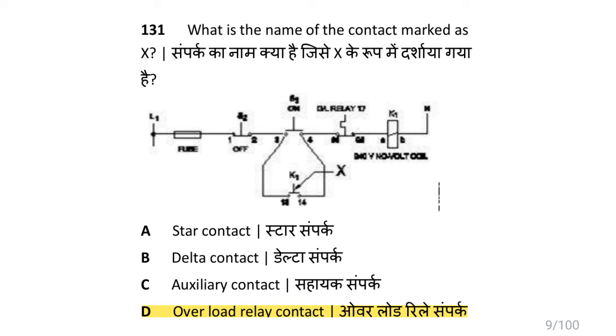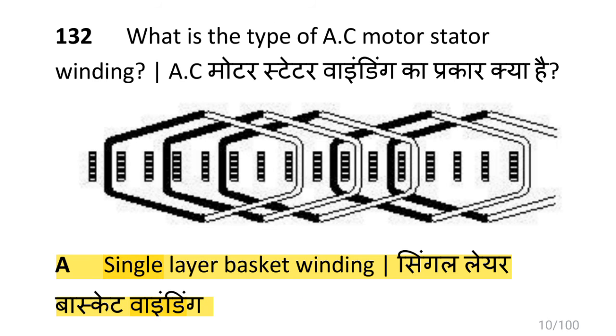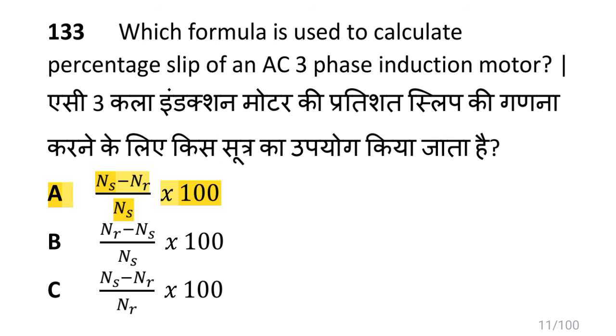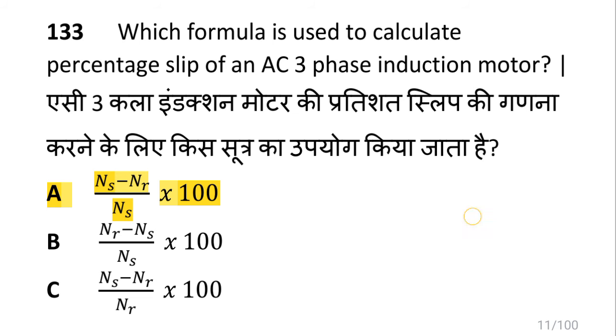The contact marked as X is the overload relay contact. The type of AC motor stator windings is single layer basket winding. The formula to calculate percentage slip of an AC three phase induction motor is: (synchronous speed minus rotor speed) divided by synchronous speed, multiplied by 100.